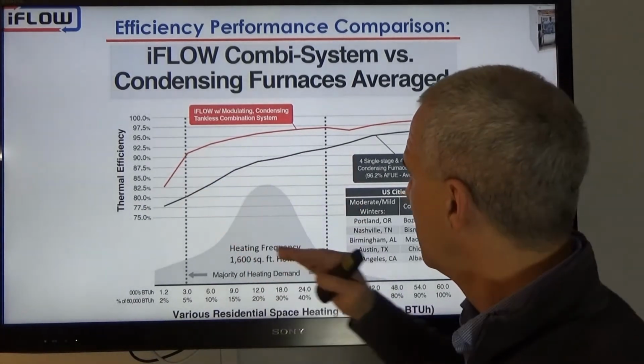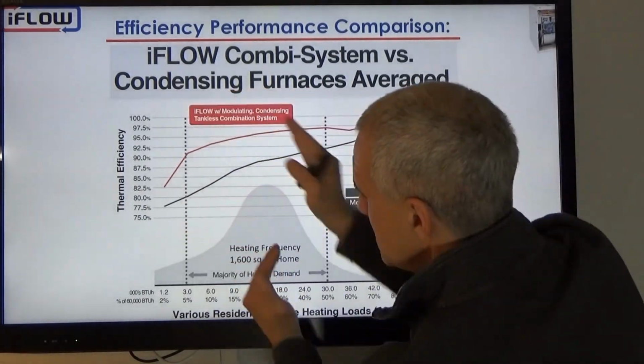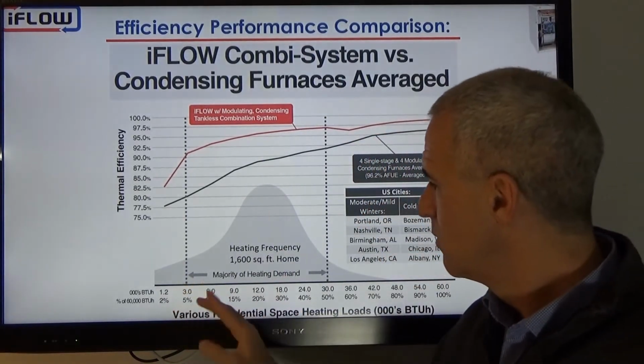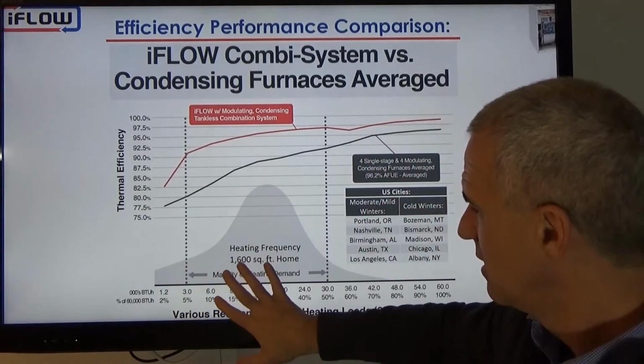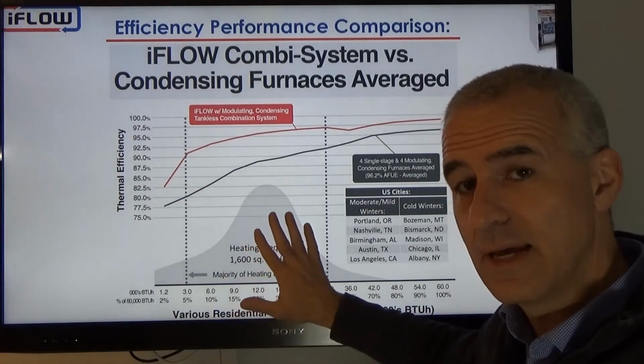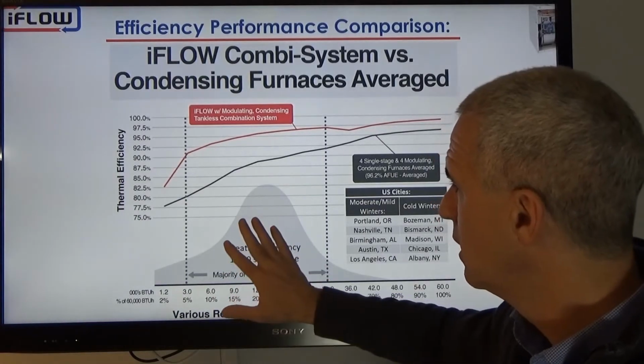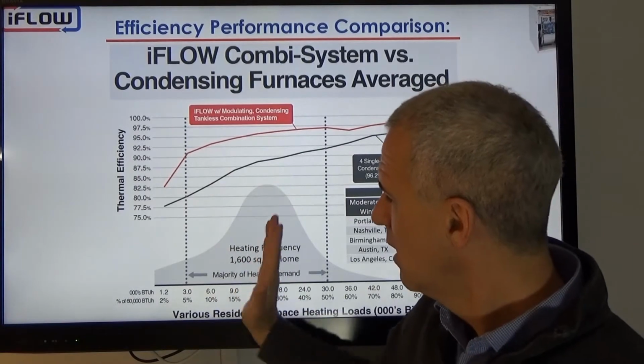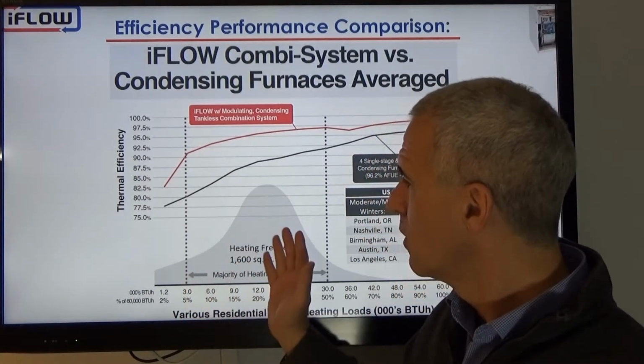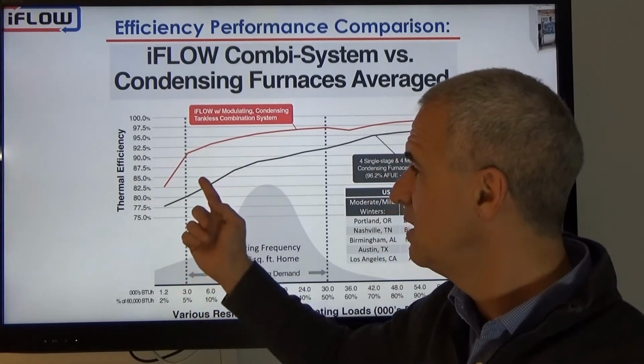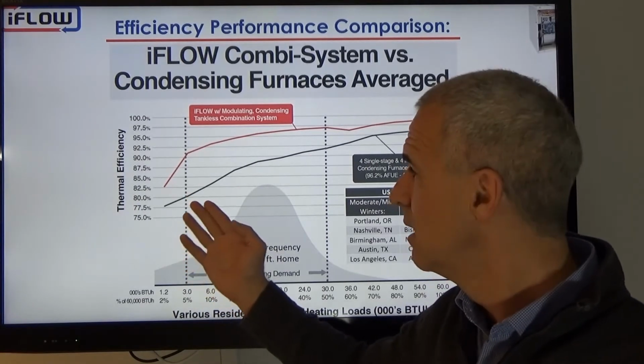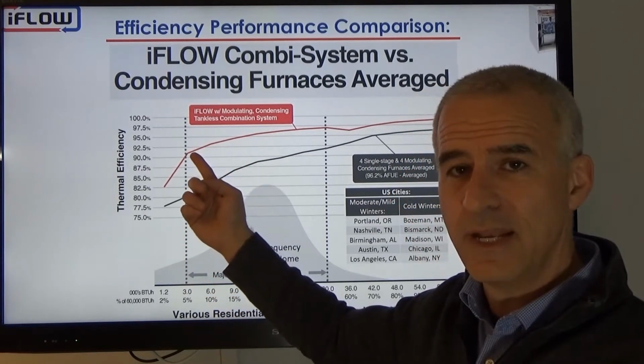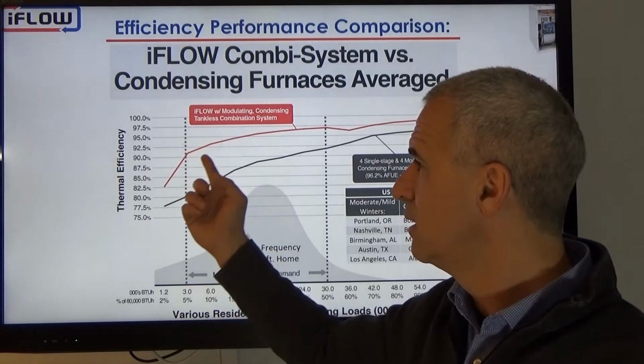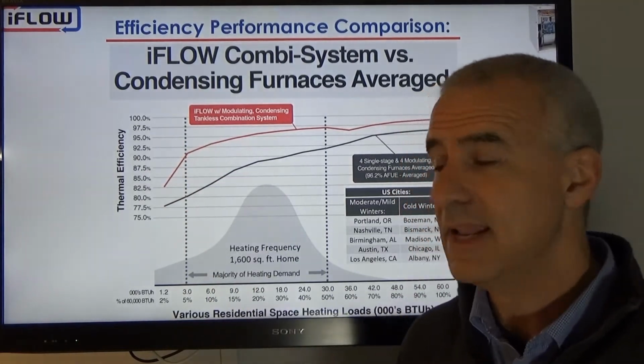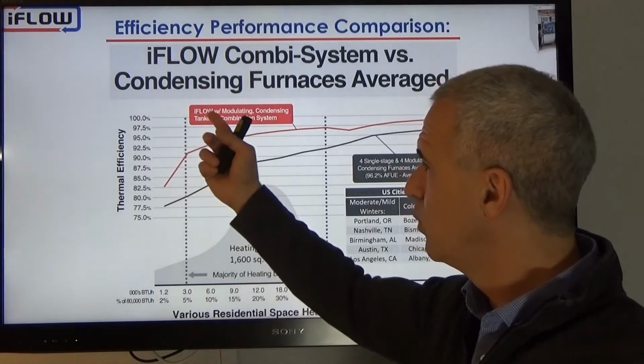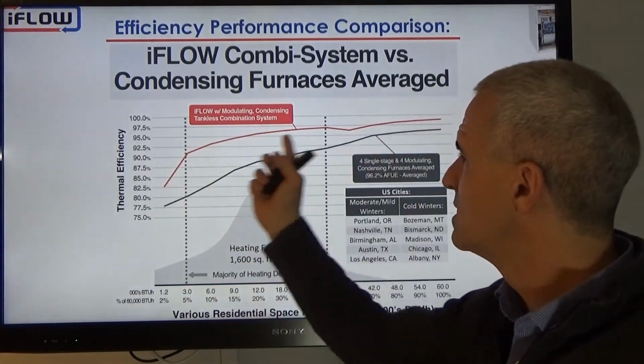Now, why is that curve getting wider as we get to the lower BTUs? Right? We've overlaid it with the actual heating distribution from the US houses that we explained earlier. And it makes sense. The lower the input, the more cycling the furnace, the worse the system efficiency is going to be. And that's where the iFLOW and the Navien pick it up because of the lower minimum input capability of the Navien, and when it's paired with the iFLOW, we deliver that performance into the house.